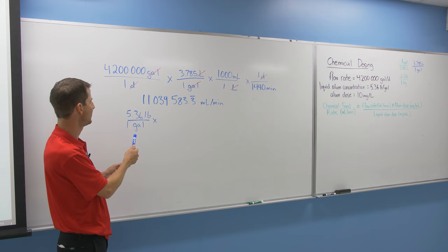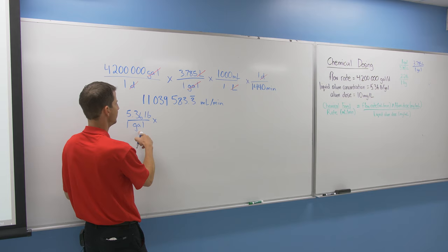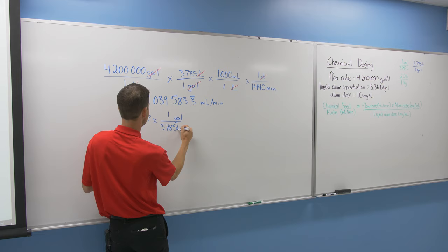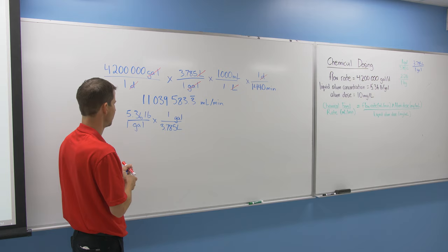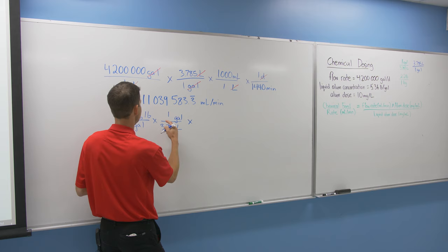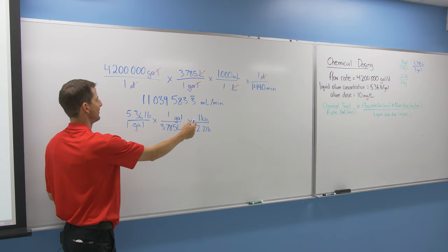Next, we're looking at the liquid alum concentration, given at 5.36 pounds per gallon, and we'll use our conversion factors again. Gallons are on the bottom, so the gallon needs to be on top. One gallon is 3.785 liters. That takes care of our gallons. Now let's convert pounds to kilograms—let's get those imperial units out of the way. Pounds are on top, so pounds go on the bottom: 2.2 pounds in one kilogram. Now we've got kilograms per liter.